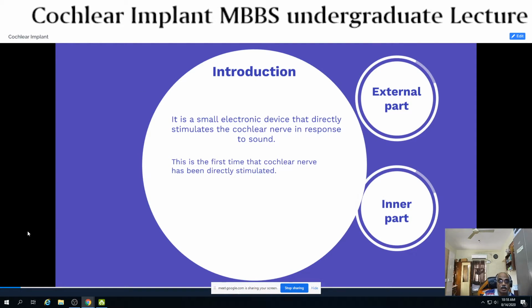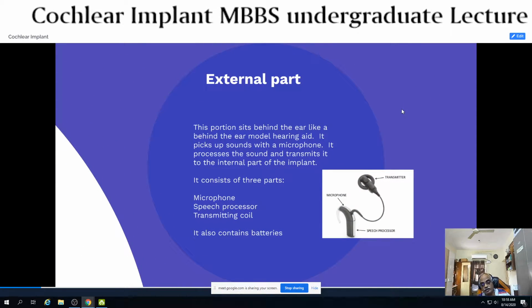And this cochlear implant per se has two parts. One happens to be the external part. The external part usually sits behind the ear, as we saw in the behind the ear model hearing aid, which we discussed in our last session. In the picture you will be seeing, it more or less resembles the behind the ear model hearing aid. This component contains a microphone, a speech processor, and a transmitting coil. This is the transmitting coil, this is the transmitter. So, this entire unit is the external unit, and of course, the lower portion of this box or container contains a battery.